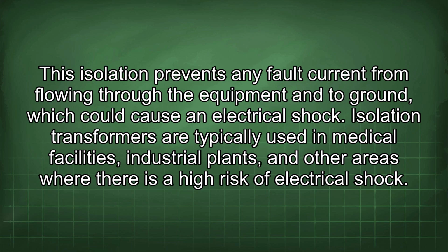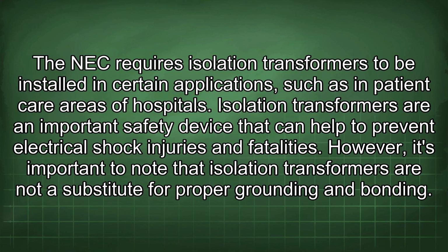shock. Isolation transformers are typically used in medical facilities, industrial plants, and other areas where there is a high risk of electrical shock. The NEC requires isolation transformers to be installed in certain applications, such as in patient care areas of hospitals. Isolation transformers are an important safety device that can help to prevent electrical shock injuries and fatalities. However, it's important to note that isolation transformers are not a substitute for proper grounding and bonding.